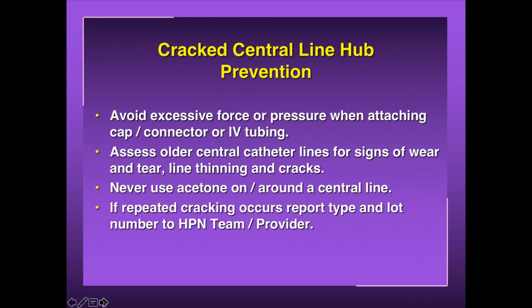So to prevent it, don't use too much force when you're attaching things, and keep an eye on your older catheter, just looking for wear and tear. If you notice there's a thin spot, never use acetone around your line. That will cause damage to the line. It thins out the polyurethane. It makes it weaker. And if you're seeing a lot of cracking frequently, we just want to make sure that we assess if there's a problem with the line itself. Maybe there was a bad production lot or something like that. So make sure we notify the team and the vendor. Next slide.